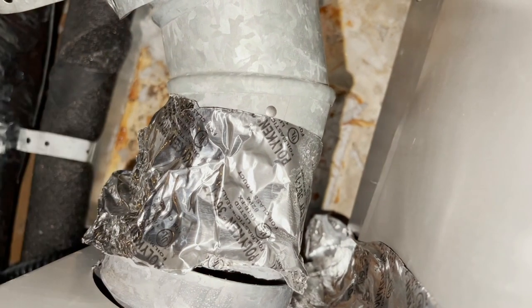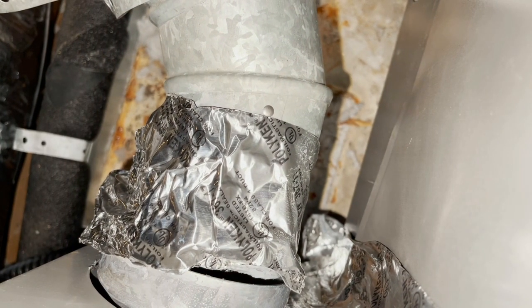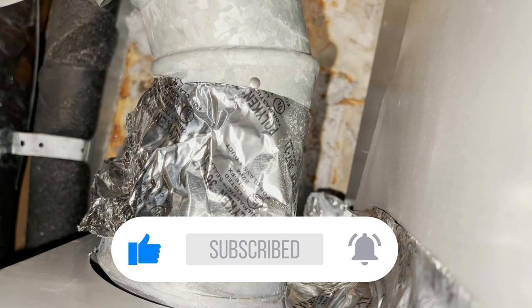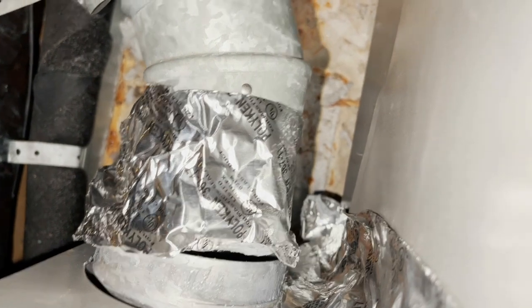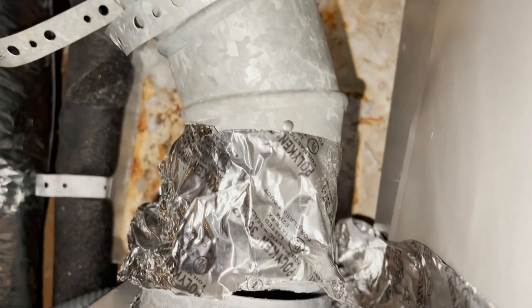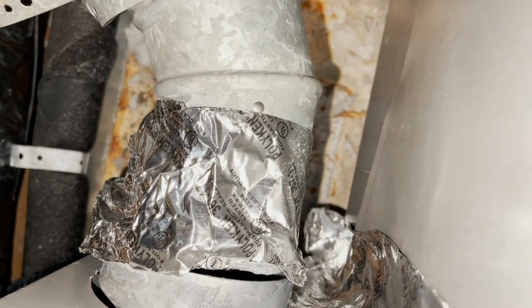I'm doing a maintenance checkup on a Lennox — two Lennox gas furnaces. This is the three-ton, and you can see where it increases from three to four inch. Must have been an old ICP — yeah, I can see the panel's an old ICP here, that would do that.